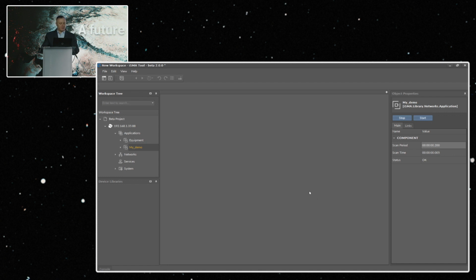The next container is the network container. Under that container we add network communication protocols. Because the system is natively designed to be ready for BACnet and Modbus, those are included by default. We also have local I/O, a dedicated network protocol that lets us get data from inputs and outputs, and here we have a haystack service—I'll talk a bit more about that in a minute.